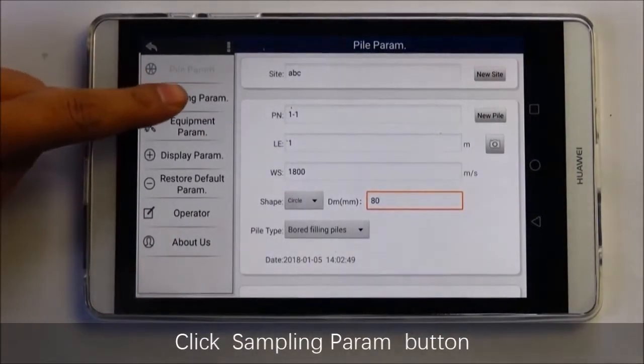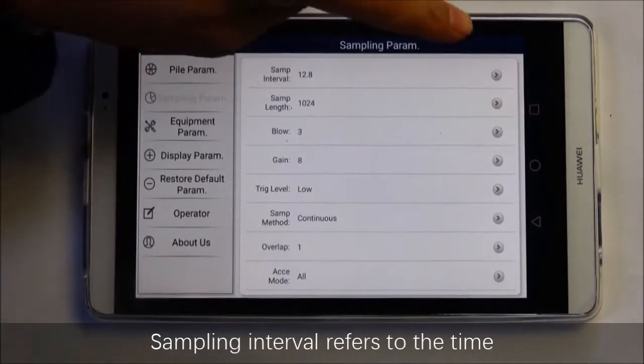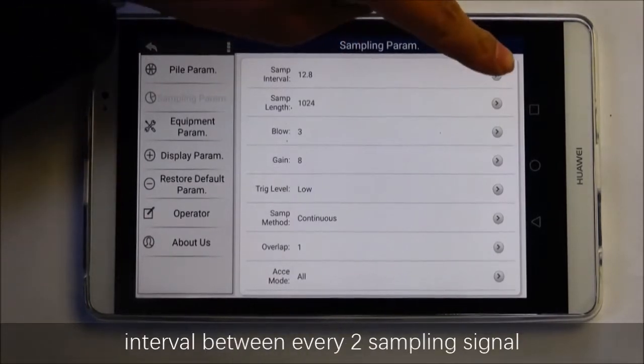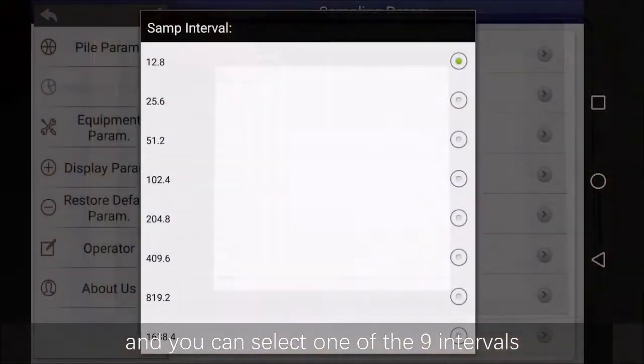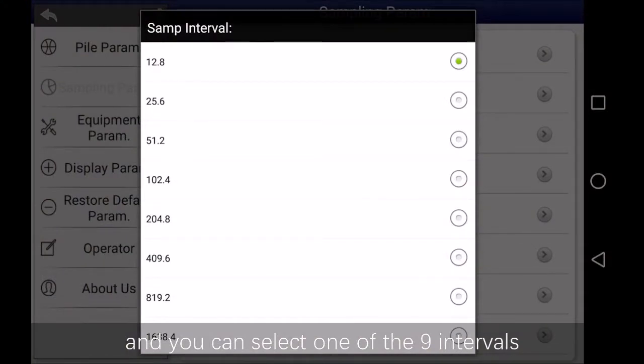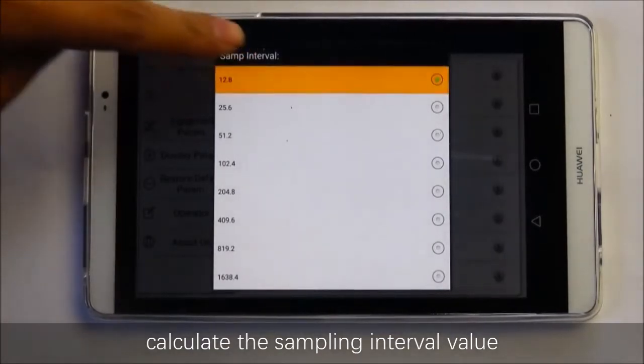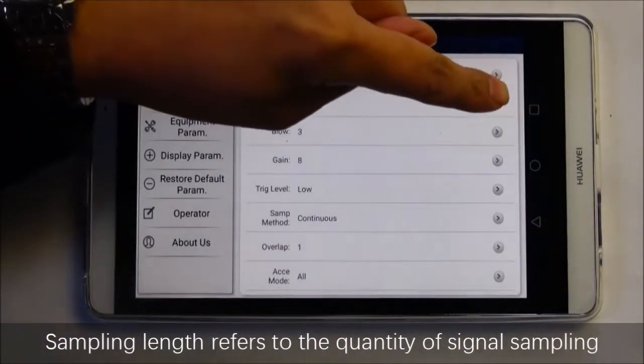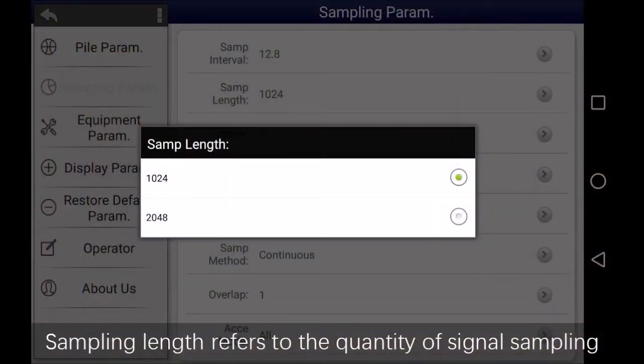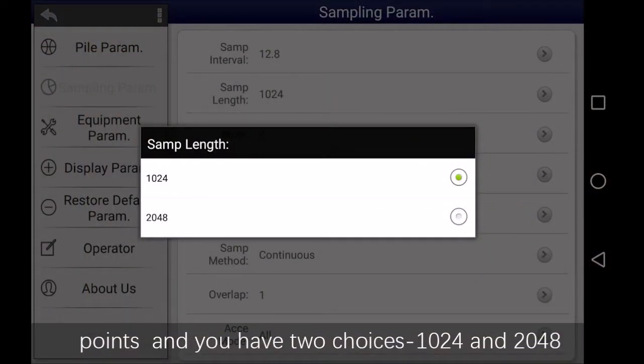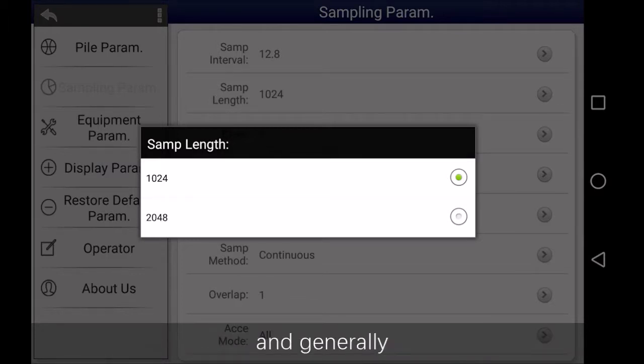Click the sampling parameter button. Sampling interval refers to the time interval between adjacent sampling signals. You can select one of nine intervals. The value can be set or not, but the pile length and velocity must be set before sampling so it will automatically calculate the sampling interval value. Sampling length refers to the quantity of signal sampling points. You have two choices: 1024 and 2048.